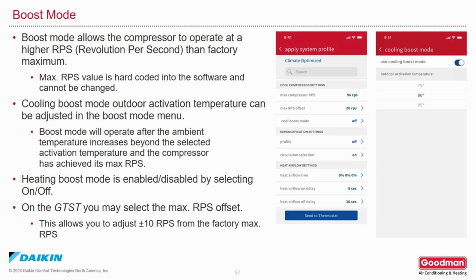Let's talk about the boost mode. The boost mode allows the compressor to operate at a higher speed than the factory maximum. Maximum RPS value is hard-coded into the software and cannot be changed. Cooling boost mode outdoor activation temperature can be adjusted in the boost mode menu. Boost mode will operate after the ambient temperature increases higher than the selected activation temperature and the compressor has achieved its maximum revolutions per second.